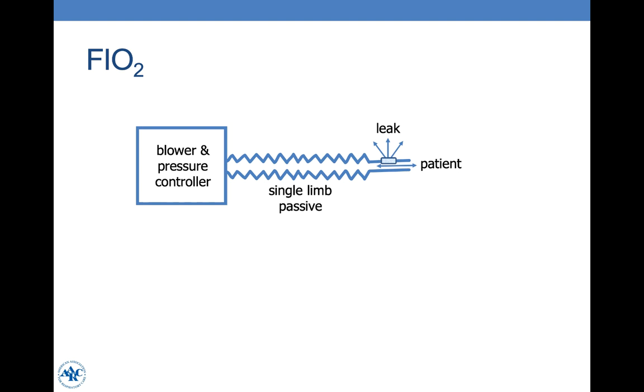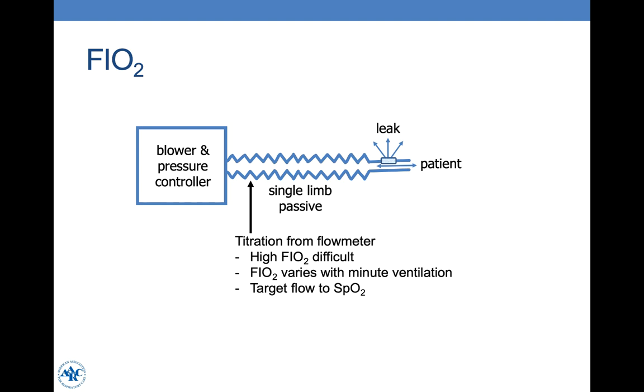Returning to the cartoon of the bi-level device — some devices have a blender, allowing us to set FiO2 directly as we would on an ICU ventilator. However, some devices do not have an internal blender, so we will need to titrate oxygen into the circuit from a flow meter. With the titration approach, it is difficult to deliver a high FiO2, and the FiO2 will vary with minute ventilation — if minute ventilation increases for the same oxygen flow, FiO2 will decrease, and vice versa. With either approach, target FiO2 based on oxygen saturation measured by pulse oximetry.